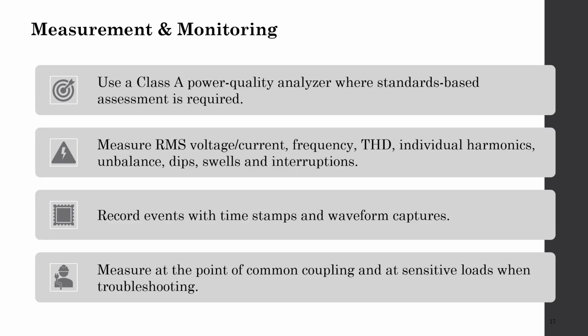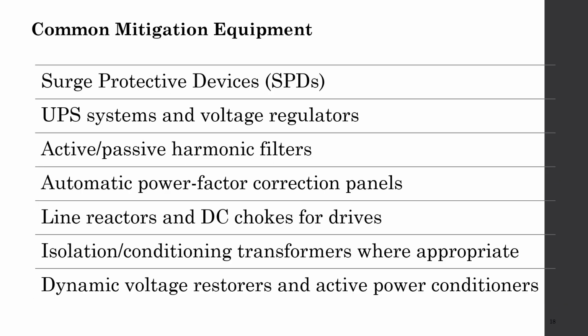Measurement and monitoring. Use a Class A power quality analyzer where standards-based assessment is required. Measure RMS voltage, current, frequency, THD, individual harmonics, unbalance, dips, swells, interruption. Record events with time stamps and waveform captures. Measure at the point of common coupling and sensitive load when troubleshooting. Common mitigation equipment: surge protective device, UPS, voltage regulators, active and passive harmonic filters, automatic power factor correction panel, line reactors and DC choke for drives, isolation and conditioning transformers where appropriate, dynamic voltage restorers and active power conditioners.